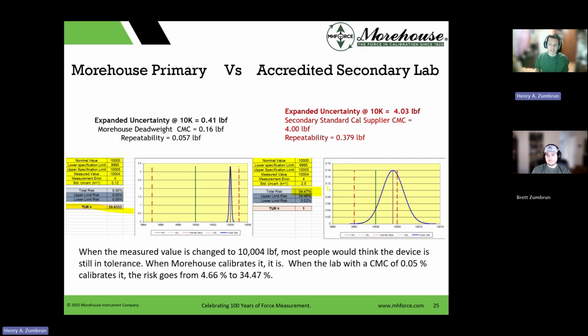If you don't take uncertainty into account and you give this to somebody and say, I measured it and it read 10,004, this specific risk curve is saying there's a 34.47% chance that you're saying it's good when it's actually bad. Is that a number you want to take back and look at on that likelihood and consequence matrix? And is it critical? That's what you have to decide.